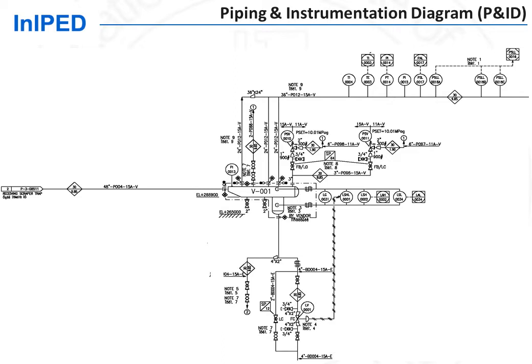P&IDs do not only show the main process lines as process flow diagrams do, but all lines, including utility lines, lines used for maintenance, for equipment drainage and depressurization, lines used for startup, and all other possible use. In addition, the P&IDs show the line diameters as well as material of construction and rating. All valves are shown, not only control valves as on the process flow diagrams, but manual valves as well. All instruments are shown, not only process control instruments, but also instruments used for monitoring, as well as alarm and process shutdown.